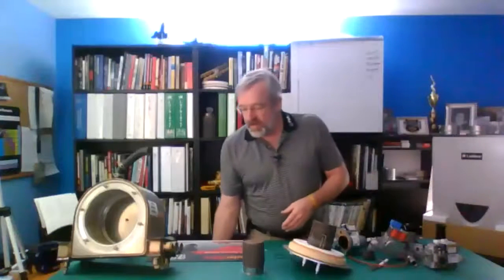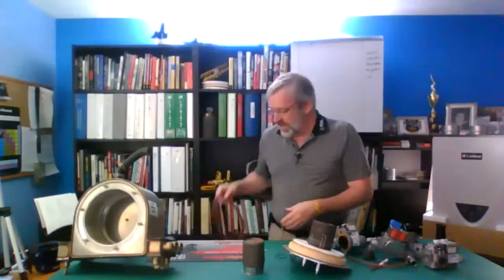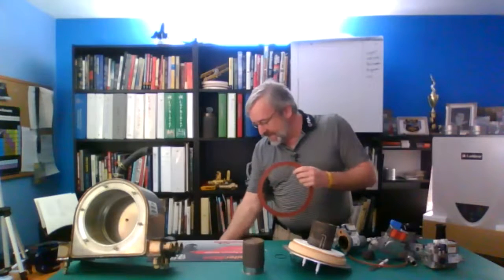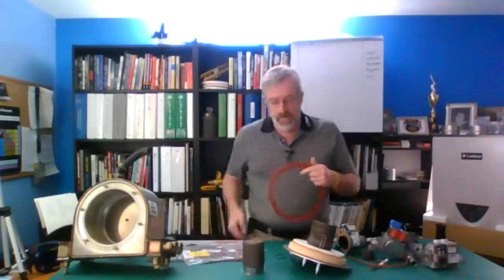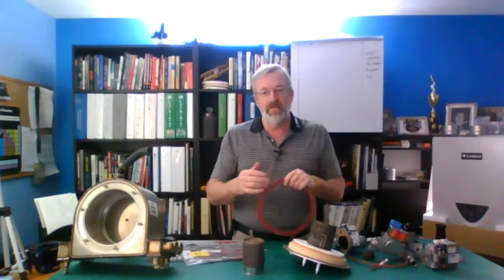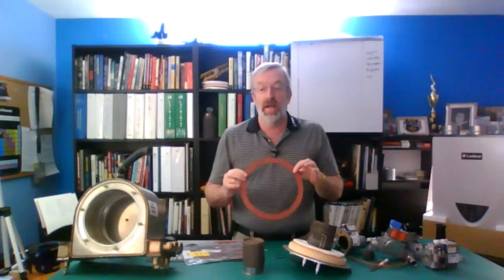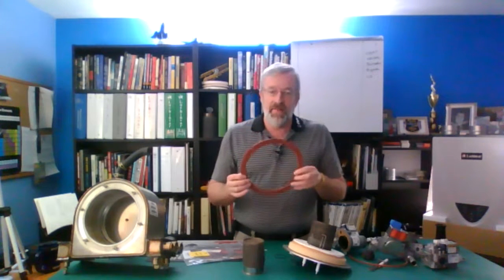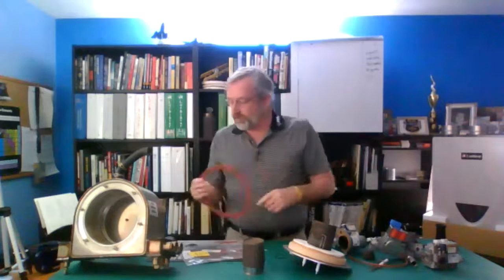When I'm in the fire tube designed units, we have two styles of gaskets in there. The newer style uses this red rubber gasket. Now this is generally reusable when you take it off. What's the exception to that rule? Maybe I've had one of these that's been in 4 or 5 years and I've never opened it. I might have a hard time taking that gasket apart without damaging it. But if you're pulling apart every couple of years, you'll get some reuse out of this one.